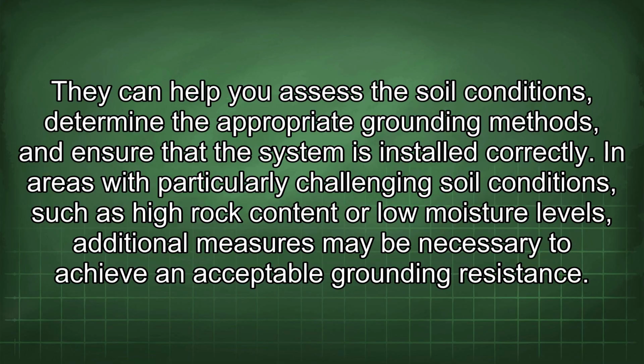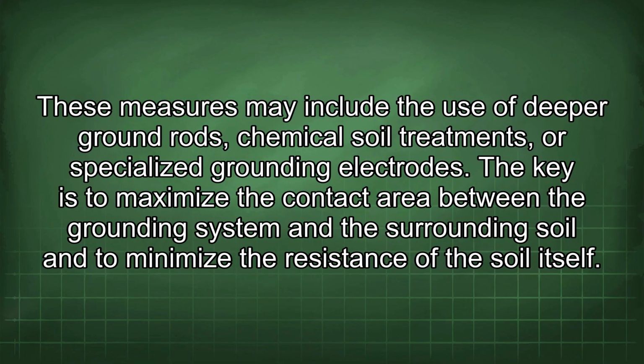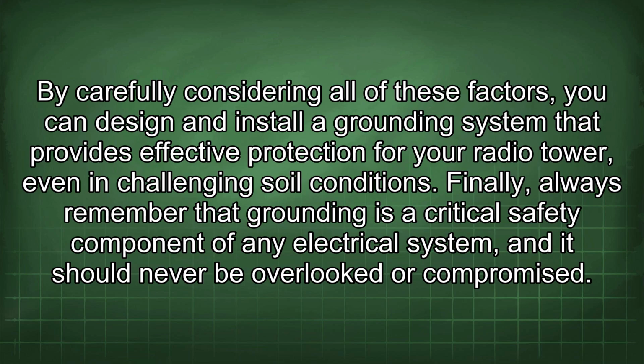In areas with particularly challenging soil conditions, such as high rock content or low moisture levels, additional measures may be necessary to achieve an acceptable grounding resistance. These measures may include the use of deeper ground rods, chemical soil treatments, or specialized grounding electrodes. The key is to maximize the contact area between the grounding system and the surrounding soil and to minimize the resistance of the soil itself. By carefully considering all of these factors, you can design and install a grounding system that provides effective protection for your radio tower, even in challenging soil conditions.